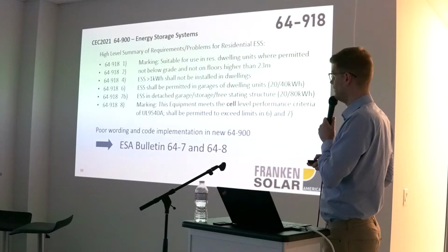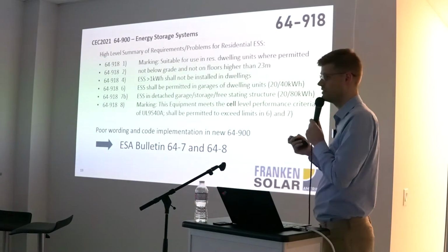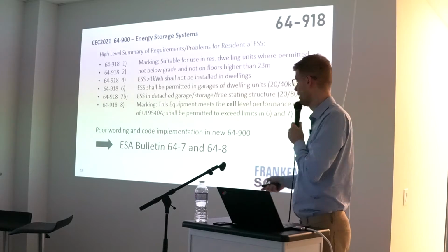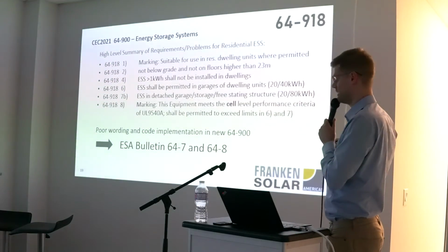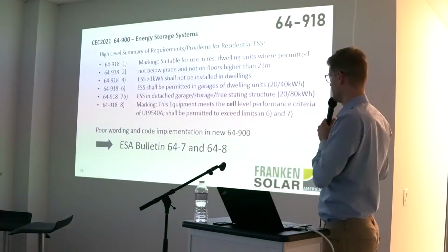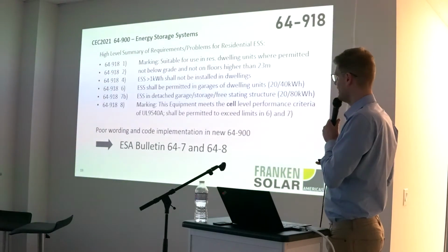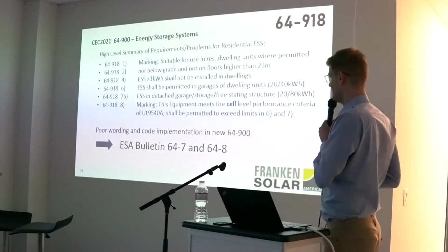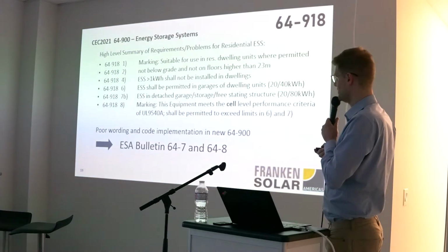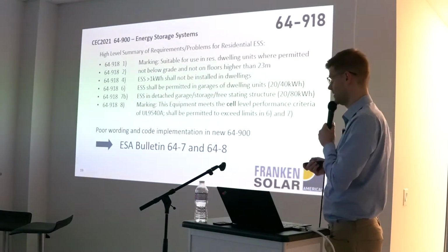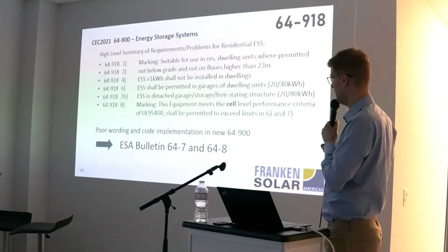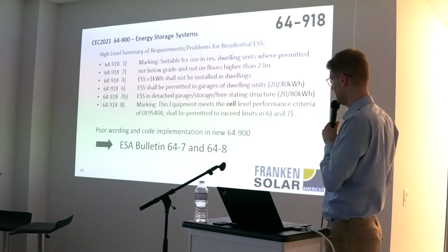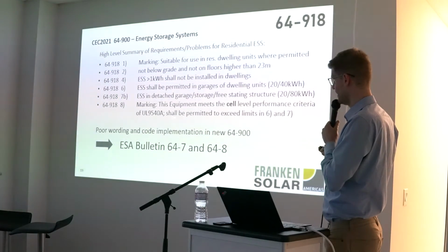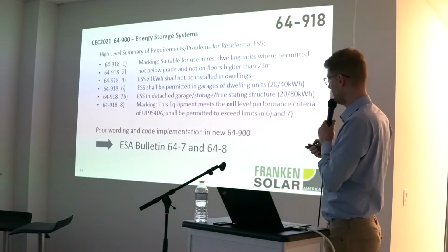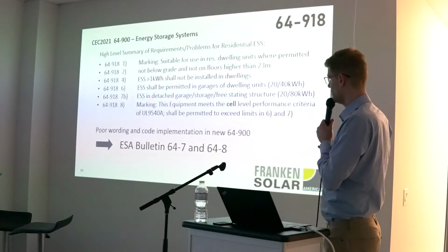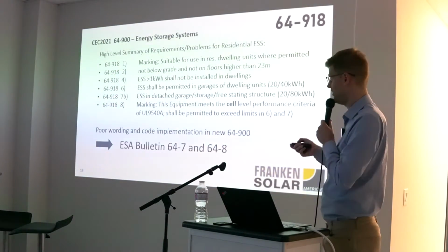And then if you have a detached garage, a storage, or even a freestanding structure, so something that is completely detached from your building, then you can even go in 20 kilowatt increments up to 80 kilowatt hours of that system. And then lastly, and that's one of the big topics which we just have discussed, ideally to be compliant, the marking needs to be: this equipment meets the cell level performance criteria of UL9540A, shall be permitted to exceed. That's the first part that no system can achieve. So this is already off.